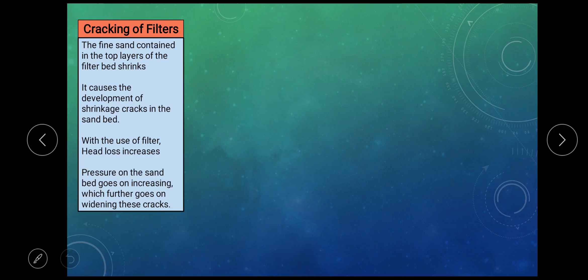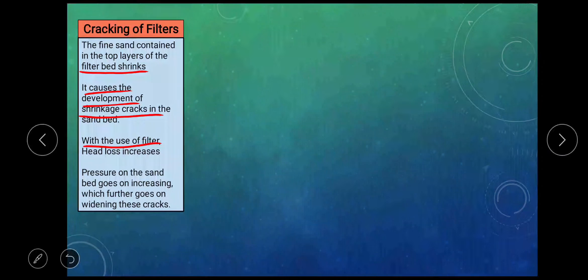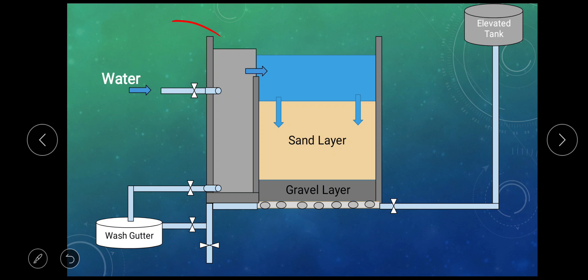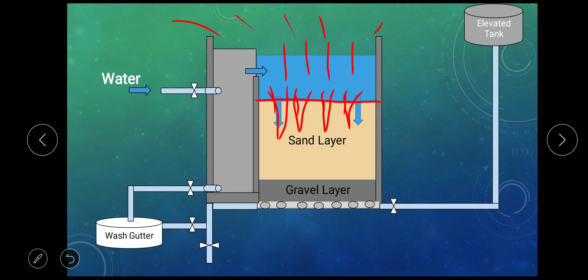Cracking of the filter: The fine sand contained in the top layer of the filter bed shrinks, causing shrinkage cracks on the sand bed. With use of the filter, head loss increases, which increases the pressure on the sand surface. This pressure will widen the cracks on the surface of the sand. Due to atmospheric conditions, the sand layer develops small cracks. With the passage of time, constant pressure from the top increases the thickness and width of these cracks. Due to this widening, all the impurities get penetrated into these cracks. As the depth and widening of cracks increases, impurities can easily be seen in the filter water.